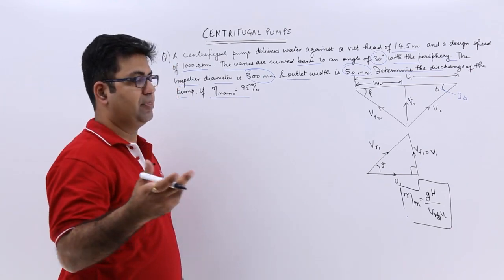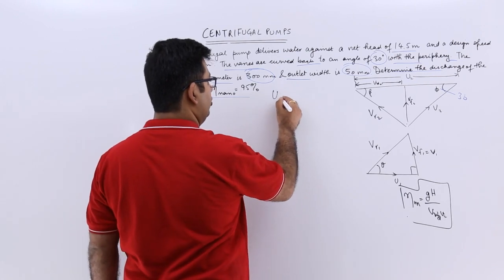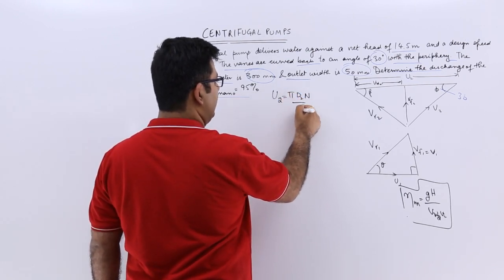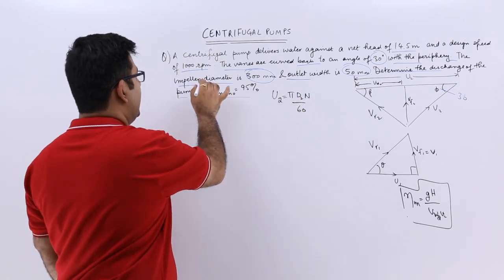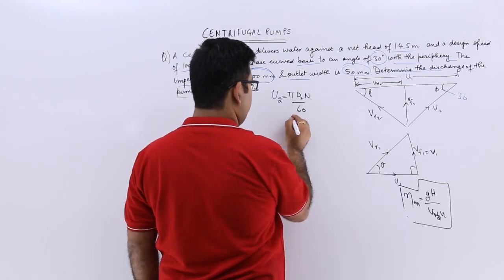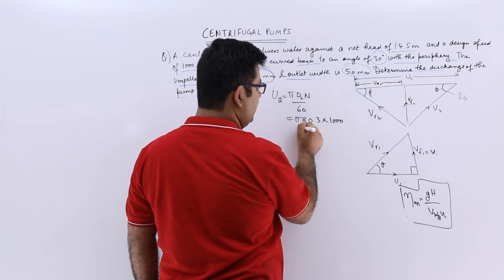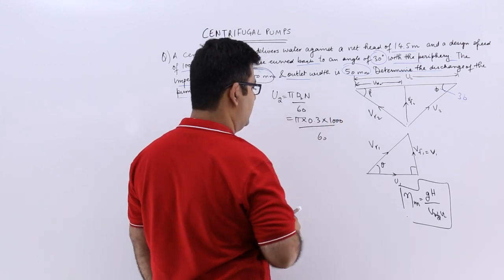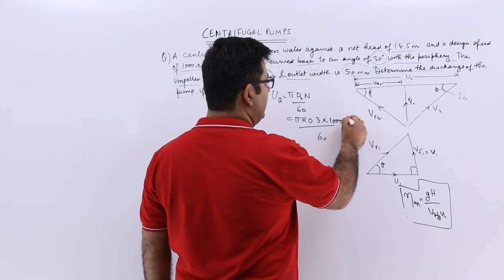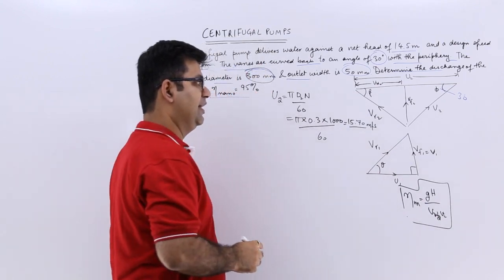Now we can easily find out the value of U2. So U2 would be pi into D2 into N by 60, because the impeller diameter at outlet is 300 millimeters. So this would be pi into 0.3 into 1000 by 60. So from here I will get a value for U2 as 15.70 meters per second.